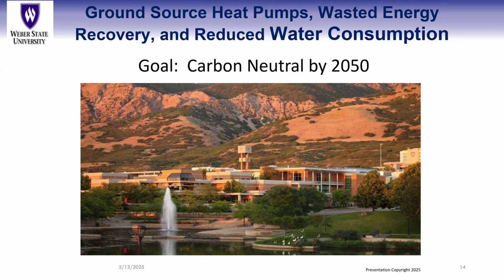For special peak loads, we actually have buildings tied to both sides of the chilled water supply and the chilled water load, and the system control decides where to draw its best temperature water, since we've got about a 12-degree differential across that system. So some buildings might be in a heating load in the morning and pull from the chilled water return, and when we start air conditioning, we might pull from the chilled water system.